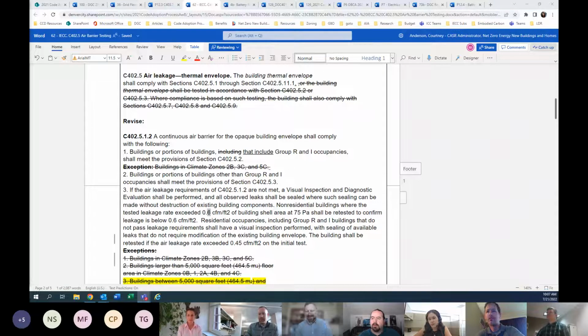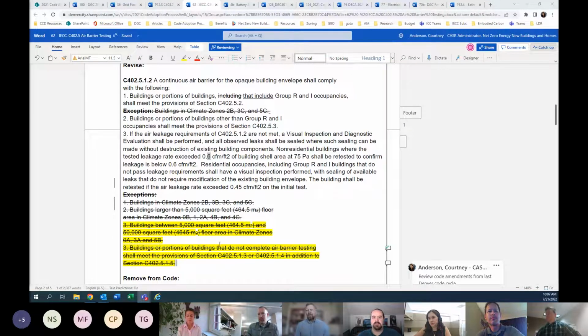He's still looking, I think. So there is an exception for buildings between 5,000 and 50,000 square feet, group R occupancies, from the testing requirement in 2021. If you wanted to make testing mandatory, the simplest way would be to just strike that exception under C402.5.1.2, under number 2. Most of what's here already has that meet 0.4. If you fail 0.4 but you're at least under 0.6, then you take these remediation steps, but you can't be above 0.6.